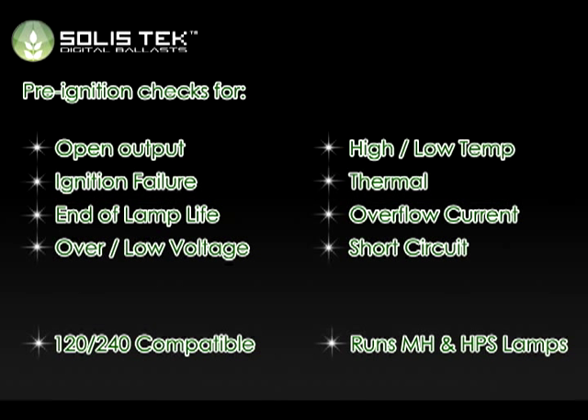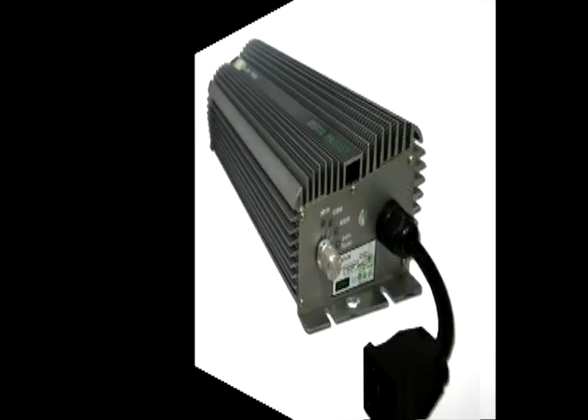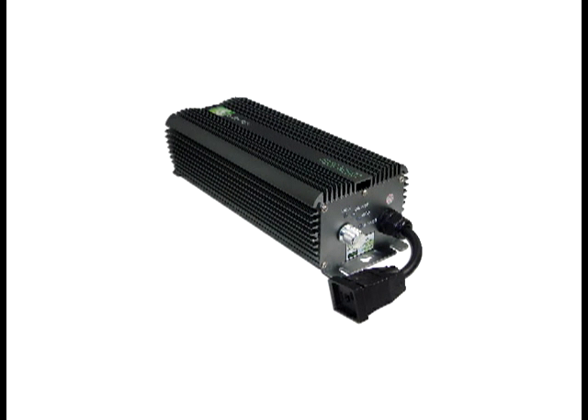Solis Tek Digital Ballast will operate both metal halide and high pressure sodium lamps. Our 1,000-watt ballast is capable of 1,000, 600, and 400-watt applications. Our 600-watt ballast is capable of 600 and 400-watt applications, and our 400-watt ballast is capable of 400 and 250-watt applications. Additionally, Solis Tek Digital Ballasts are ready to handle any voltage in the 90- to 260-volt range.